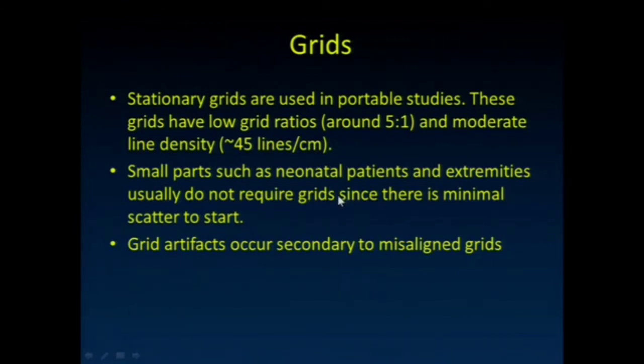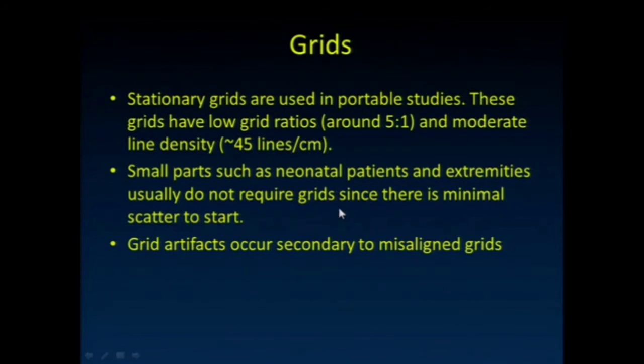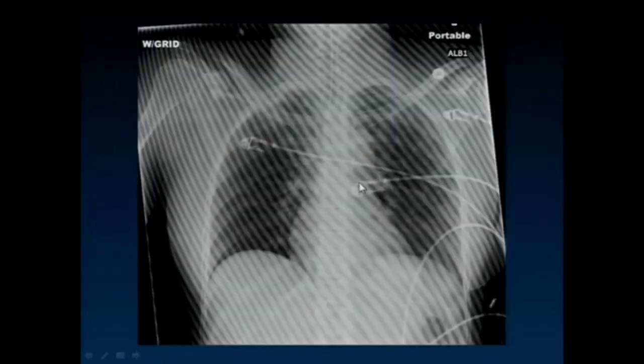For portable studies, stationary grids are used with lower grid ratios and moderate line density. Sometimes, if not placed well, you can see grid artifacts on portable studies. Small parts and neonatal patients don't require grids because there's minimal scatter to start with—adding a grid would only increase dose unnecessarily.